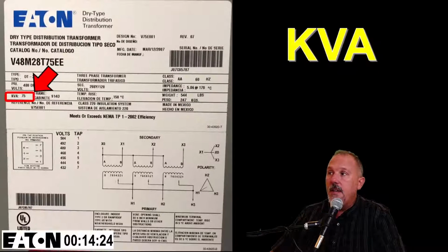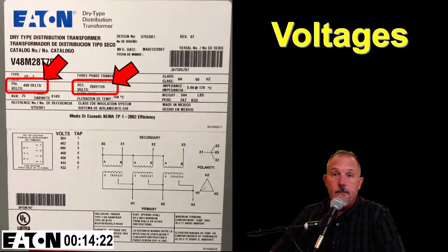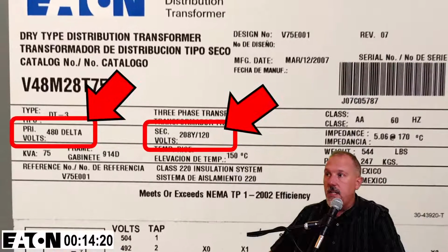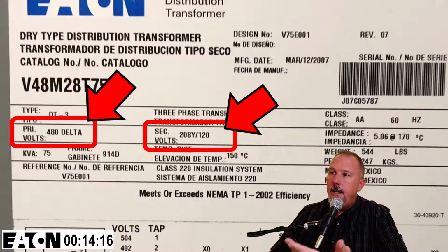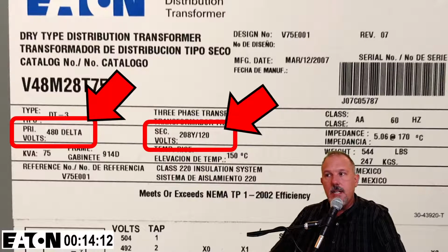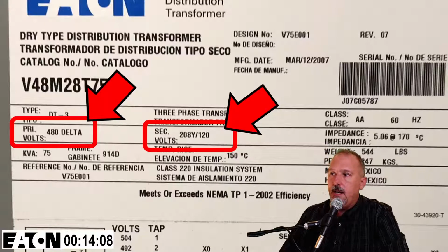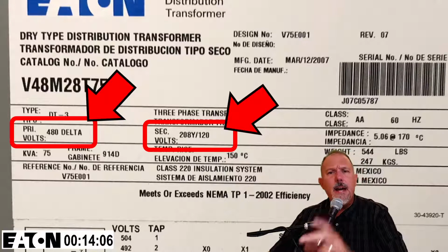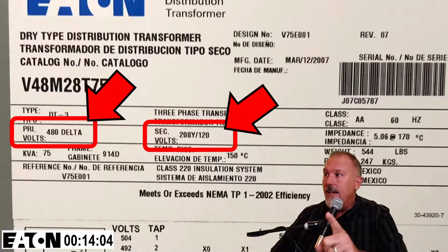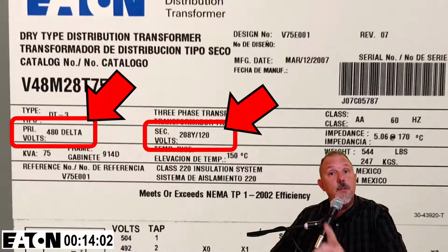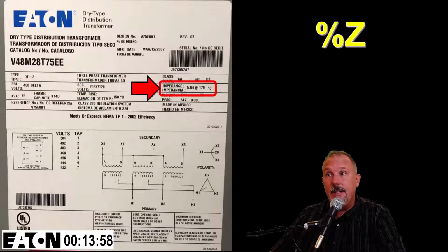The other thing that I am going to be interested in, obviously, is my voltage, right? So I need a primary and secondary voltage. In this case, this is a 480 volt delta to a 208 volt secondary Y configuration, 120 volts line to ground, line to neutral. And I'm going to need that information. Why? Because I need to determine full load amps on primary and secondary, and I need kVA and I need voltage to get that done.